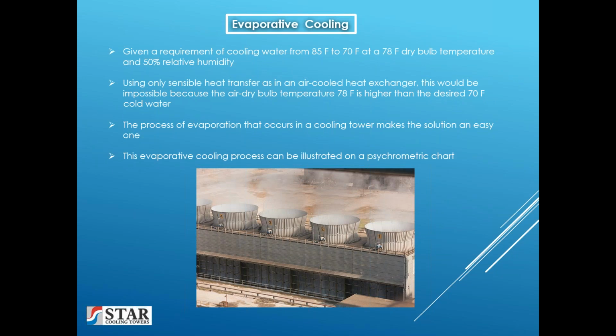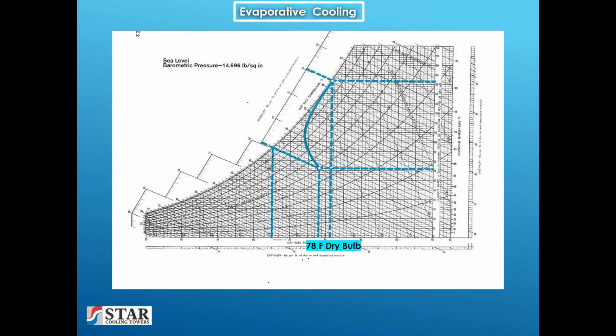This evaporative cooling process can be illustrated on a psychrometric chart. If we intersect the 78-degree dry bulb temperature at the bottom of the chart, and come up to the 50% relative humidity curve, we can come over, and at this point we see that represents a 65-degree wet bulb temperature. We have the 15 degrees that we're going from 85 to 70, so our total heat content, or enthalpy, increased from 30.1 BTUs to 45.1 BTUs, which is 15 BTUs gained from the water.